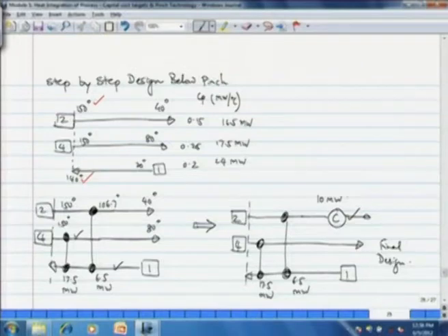Below pinch region we have 3 streams, 2 and 4 as hot streams and only 1 cold stream. Now, with the Cp inequality constraint CpH greater or equal to CpC, we can match stream 4 with stream 1. And then again we have to see which heat duty is lower. Stream 4 has 17.5 megawatt available with it and stream 1 requires 24 megawatt.